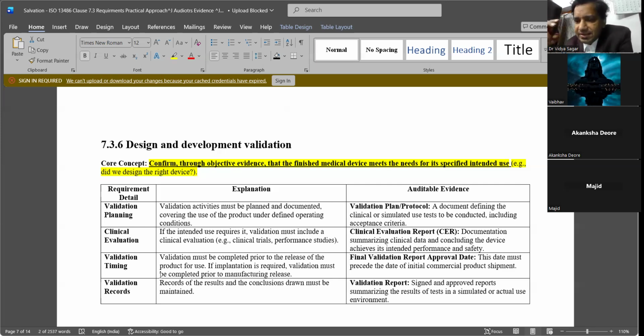My important point here is that when we are doing validation, we won't conduct validations every day or every week or every 10 days or every month. We do validations perfectly once or twice a year and say that this is validated, sterilization is validated, packing is validated. So when you are talking about validation, what exactly are you speaking about? You are meeting the intended use.